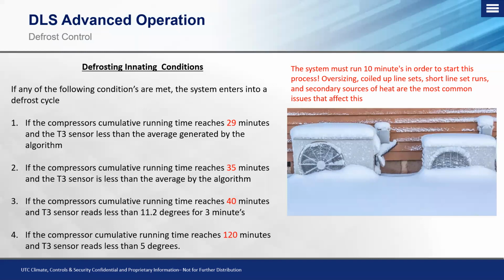Okay, so there's an average generated by the algorithm for that T3 sensor on there as it runs for that 10 minutes, that T3 sensor essentially has to drop below and reach that 29-minute runtime, cumulative runtime of the compressor to initiate a defrost cycle.